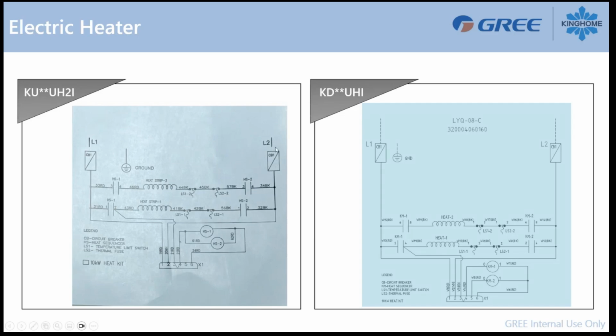You have your L1, L2 high voltage power. This voltage will apply on the sequencer. So you have a set of sequencers for your L1 and you have a set of sequencers for your L2. And then you have your limit switch, thermal fuse. You'll have all those kind of protection here. If there's not enough air or the blower motor fails, those protection will open and cut off the circuit for the heat strip.